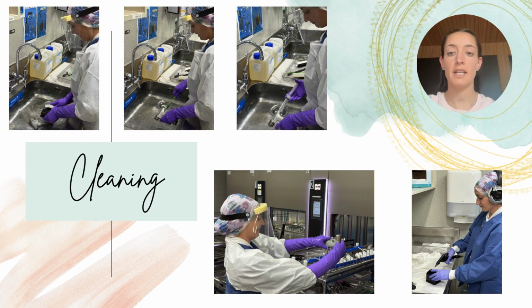The first part is about cleaning. So first of all, I'll fill up the sink with warm water up to the limits required. Then I put some detergent in it. It is already pre-programmed to have the right amount of detergent in a sink. If there is more chemical, then they could damage the RMDs, and if there is less chemical, then it won't work properly. I then disconnect the battery from the remote.